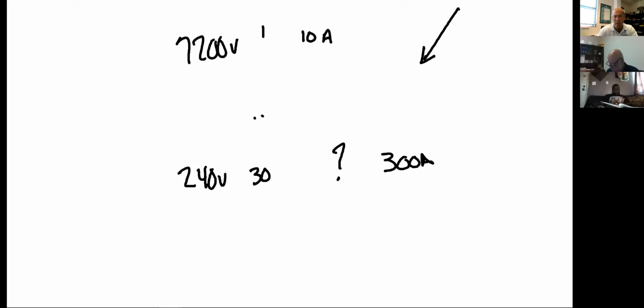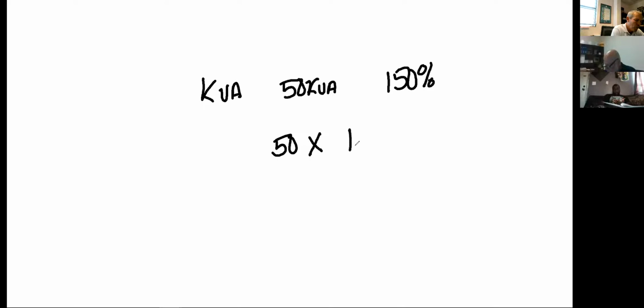Let's see. This is a simple one. How much in kVA will a 50 kVA do in overload? So it's 50 times what? 1.5. You converted 150% to 1.5, and that equals what? 75. 50 times 1.5 is 75. All right. I'm going to say that question again because you said 75,000 kVA. That's a ton of kVA. That's 7 million something.